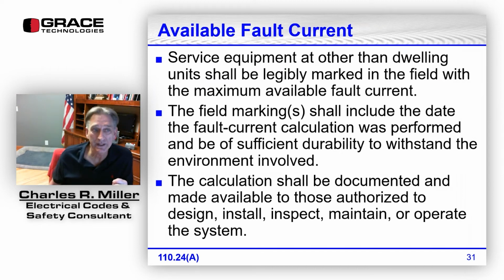So 110.24(A) says service equipment at other than dwelling units has to be legibly marked in the field with the maximum available fault current. The field markings have to include the date the fault current calculation was performed and have to be of sufficient durability to withstand the environment they're in. The calculation has to be documented. Everything nowadays has to be documented. So this is no exception, and it has to be made available to those authorized to design, install, inspect, maintain, and operate the system. So this has been in the code for a while.